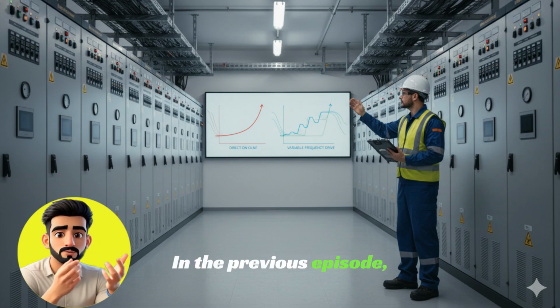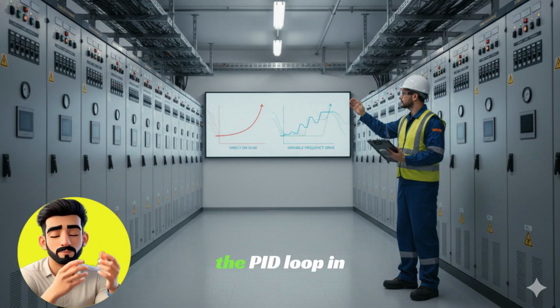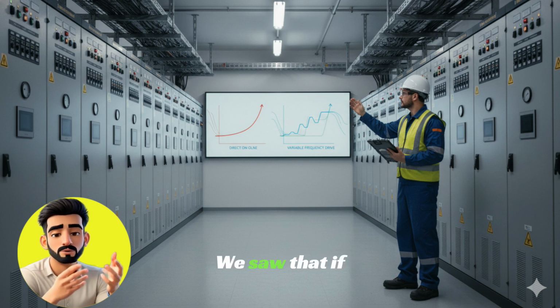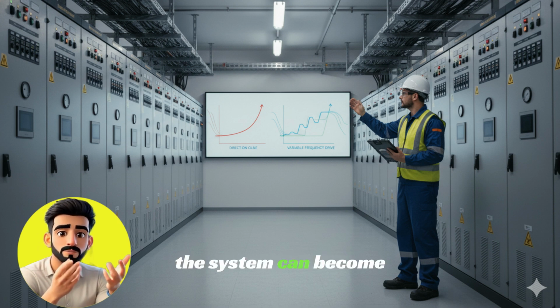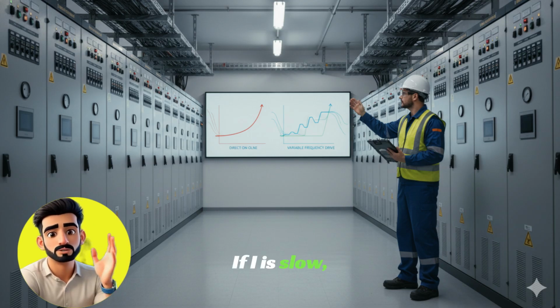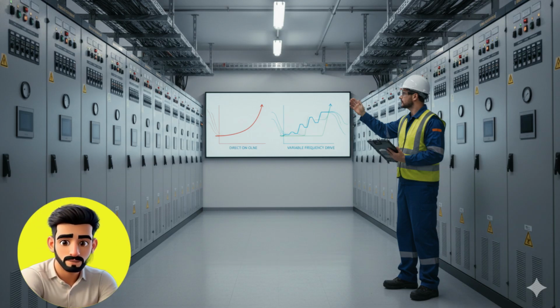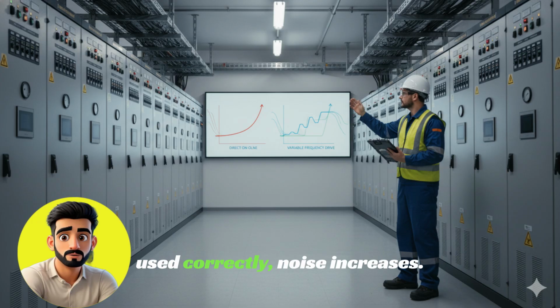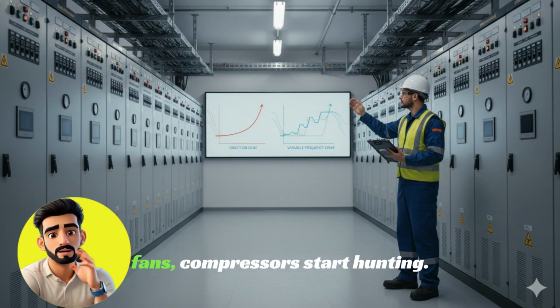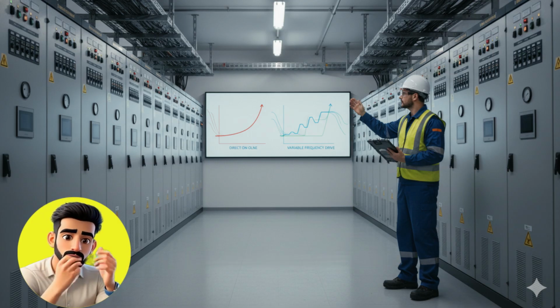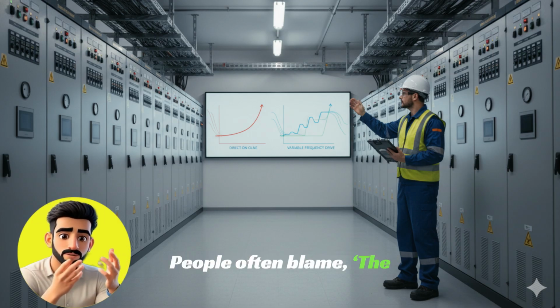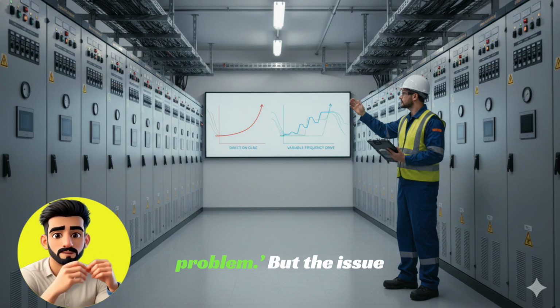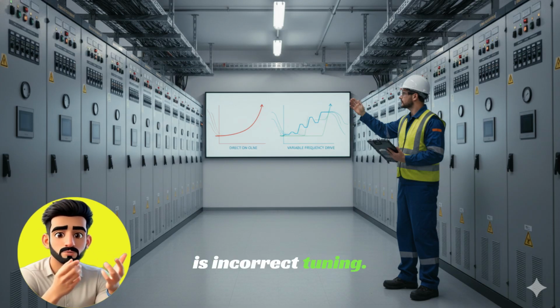In the previous episode, Part 7, we understood the PID loop in depth. We saw that if P is too high, the system can become unstable. If I is slow, the system reacts late. If D is not used correctly, noise increases, and equipment like pumps, fans, compressors start hunting. People often blame the drive for causing the problem, but the issue is incorrect tuning.